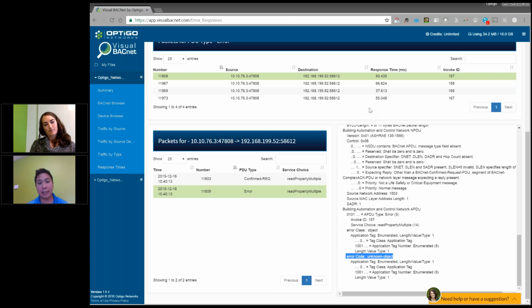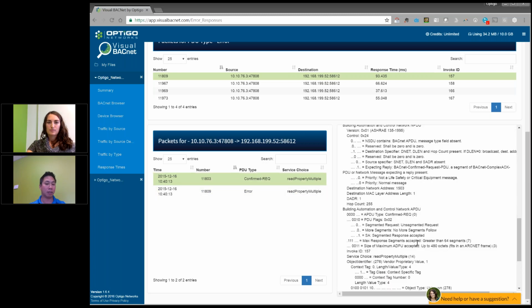To complement what Monica said, I'm quite familiar with Wireshark, and doing this there would require you to first filter for your error packets—a certain type, I think type 5—then look for the invoke ID, remove the filter, and look for all the requests to that specific device with the matching invoke ID. It's a 2-3 step process, and if you have more than one error, you could spend a good 5 to 10 minutes just finding the frame itself. If you want to flip between the two, you could mark the frames in Wireshark, but it's not that easy. Here, you just click between the two and flip between them.